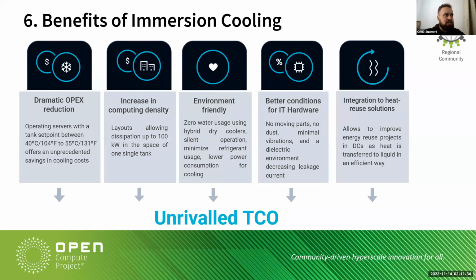So as the benefits, we will speak of immersion cooling. First, we have a dramatic OpEx reduction cost. The cooling costs of having air fans, CRAC units, air conditioners, and chillers working all the time to generate cold air are very high. While if you can set up our tanks between 40 and 55 Celsius, you can have the servers working in the immersion tanks with no throttling in a good environment, saving a lot of the cooling cost needed just to cool down that water, instead of having air conditioners pushing air through the different aisles of a data center.